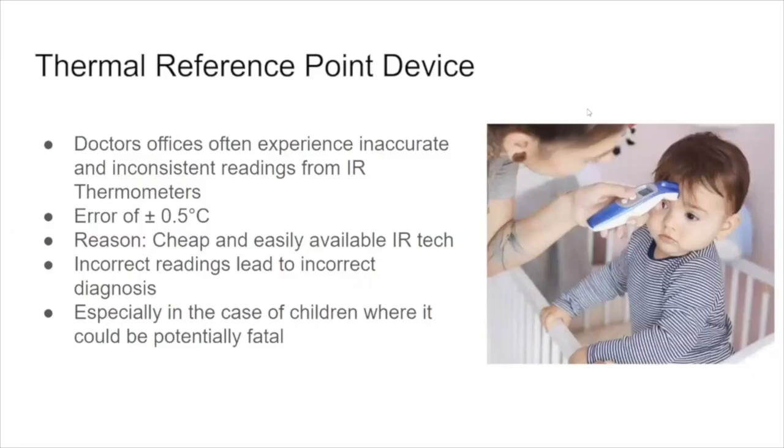Doctors' offices commonly experience the use of inaccurate and inconsistent IR thermometers. This is due to the cheap and easily available tech through means of the internet. The error in these thermometers is off by as much as 0.5 degrees Celsius.